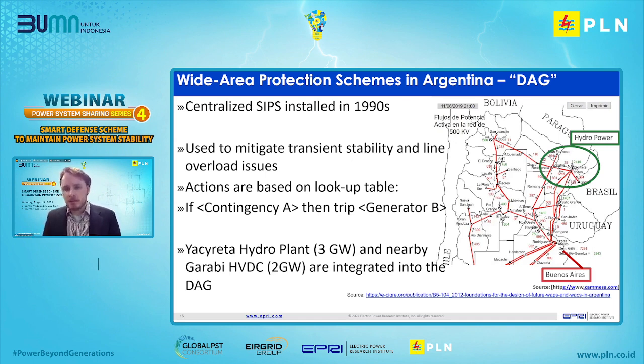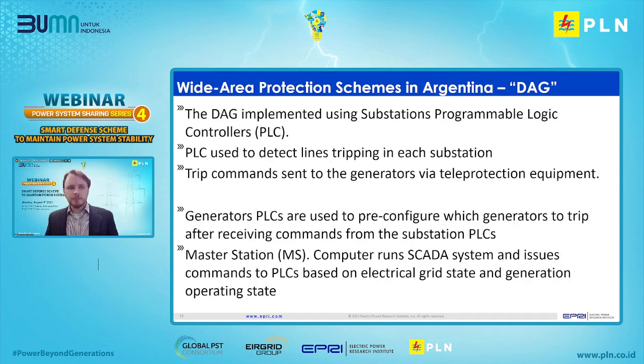In this case, this is a very large grid. So if those main transmission lines between the hydropower and Buenos Aires trip, there is up to 1,000 kilometers of line for the power to wheel around to reach the load. So this is a major scheme that was implemented and was actually called upon to activate 2 years ago, and I'll discuss that later. Moving to the next slide. This is just some information about how it's developed. Moving to the next slide, perhaps.